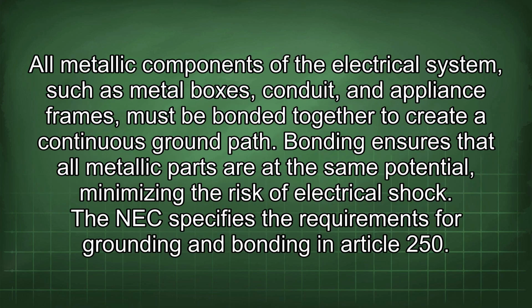All metallic components of the electrical system, such as metal boxes, conduit, and appliance frames, must be bonded together to create a continuous ground path. Bonding ensures that all metallic parts are at the same potential, minimizing the risk of electrical shock. The NEC specifies the requirements for grounding and bonding in Article 250.